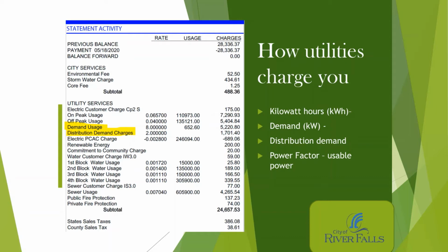The other one is power factor. Not all utilities charge for power factor, but plenty do. It's basically the usable power that you have—do you have a high power factor or a low power factor? The use of VFDs can improve your power factor and reduce that charge. So all three or four are very significant charges on the utility bill, all greatly impacted by VFDs.